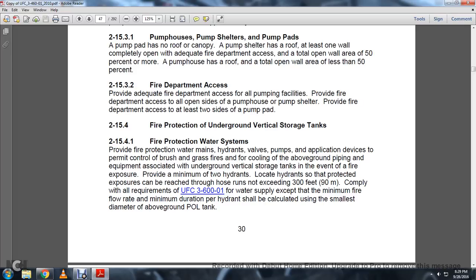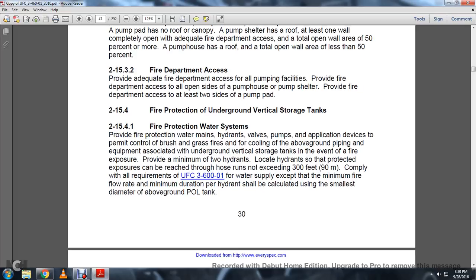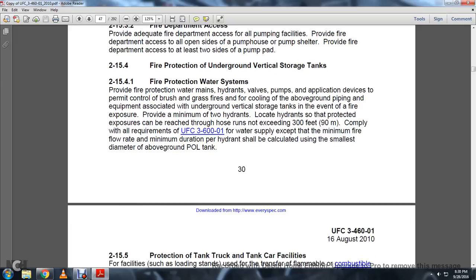Exposure can be reached through hose runs not exceeding 300 feet, complying with all the requirements of UFC 3-600-01 for the water supply, except for the minimum fire flow rate. Minimum duration per hydrant shall be calculated using the smallest diameter of the above ground petroleum oil lubricant tanks.